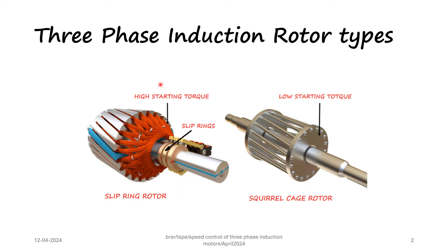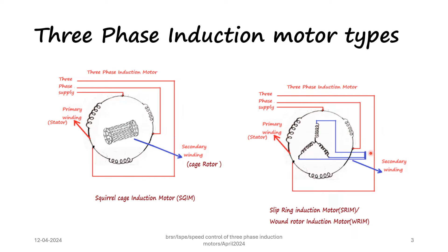In both cases the stator contains a three phase winding. The stator is shown as star connected and the three phase supply is given to the stator. The squirrel cage rotor is a completely closed structure. In the slip ring induction motor, the rotor has a three phase winding which is usually star connected; the three ends are taken out and externally shorted. This makes it possible to make external connections to the rotor for speed control, whereas it is not possible with the squirrel cage induction motor.